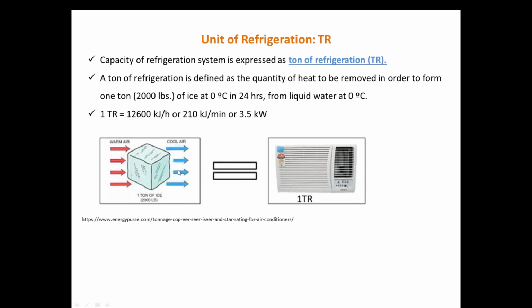I equate that definition with a device like a 1 TR AC to help you understand that whenever you go to purchase any refrigerating or air conditioning device, its capacity is expressed as TR. If you wish to purchase an air conditioner, you can say I need a 1 TR, 1.5 TR, 3 TR, or 5 TR AC. Central chillers go up to hundreds of TR, like 400 TR, 1400 TR — that kind of capacity is expressed in TR.